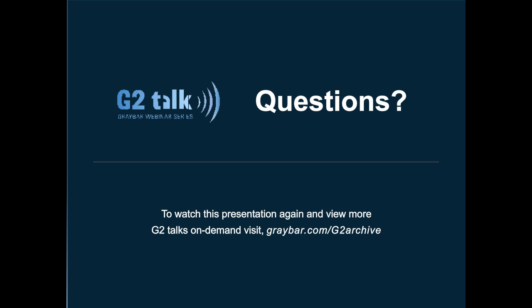So the first question we have for you, Suji, came in from Bob. He says, why is the cable ground not a good path? So the cable ground is not a good path because with the high frequency that the VFD provides, that pulse width modulation, as you increase your frequency, the resistance of the cable ground increases. And when that resistance increases, the common mode current finds a different path to ground because it's going to avoid the higher resistance path. So that's why it is not a good conductor for high frequency systems. Does that make sense? Yeah.